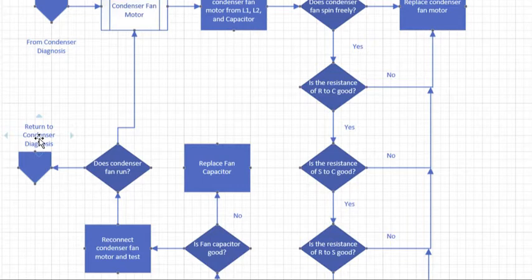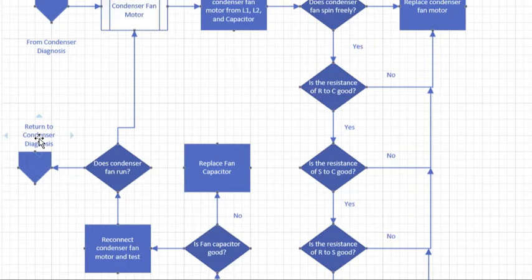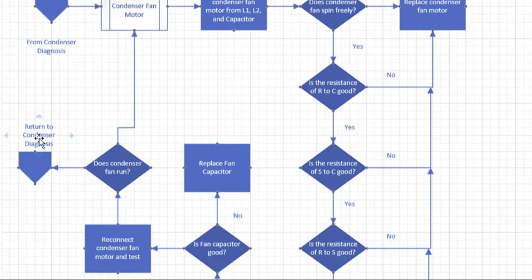We would jump back and continue on with our condenser diagnostics. But it's real easy if you do it the same way every time: disconnect motor, check for bearings, check the resistances of windings, check resistance to ground, check the fan capacitor. You're going to do it the same way every time. You'll never miss a step.